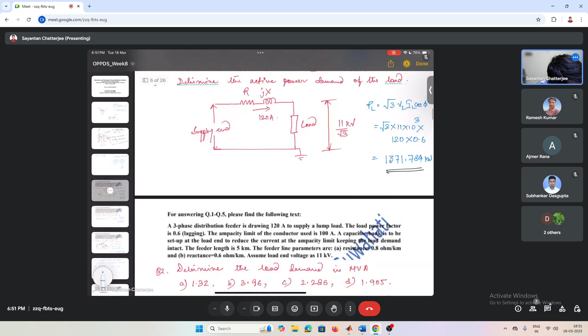So this much amount of reactive power will be needed: 1905 square minus 1371, that is 1321.8. So this is the kVAR, this is the kVAR that is required. This is the kVAR that is being supplied by the feeder. So the remaining amount of this is the required one. So highlight this, this is the required one.